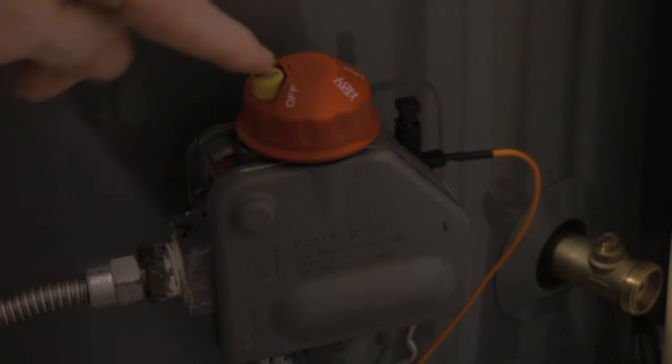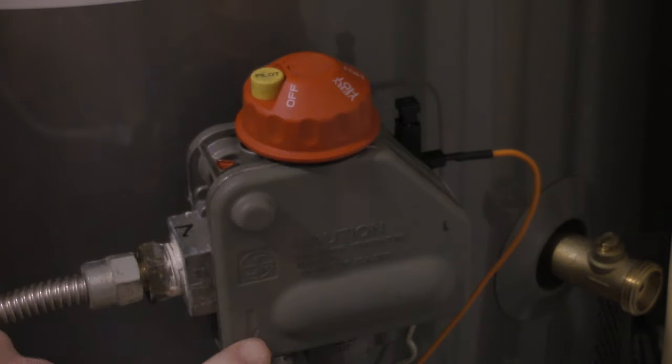And what happens is when you line this up and you push that pilot button down, it opens the gas solenoid in here, which allows gas to flow down to your burner and to your pilot light.